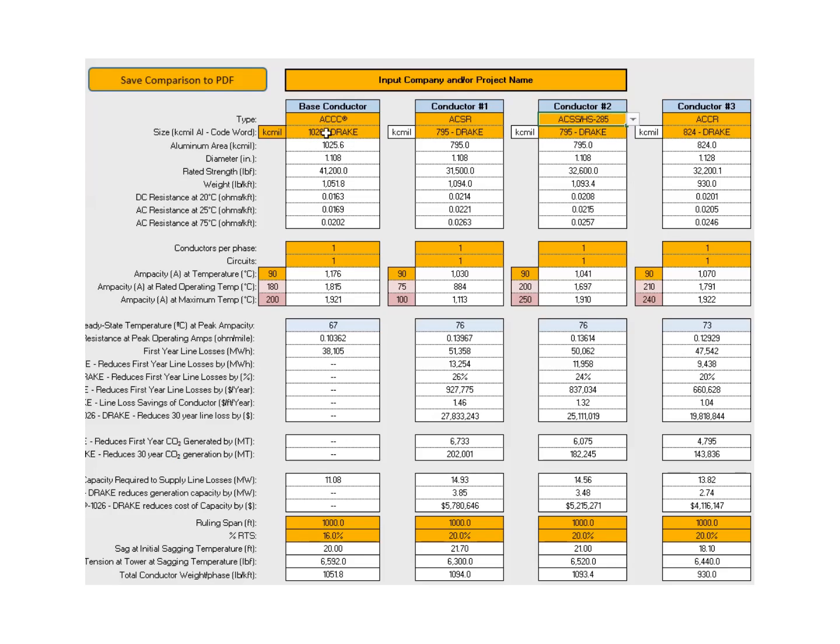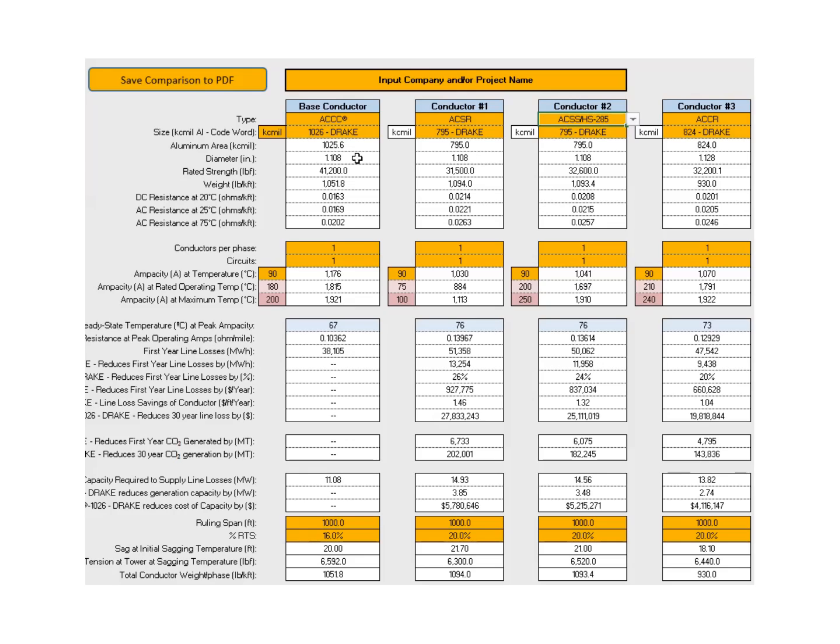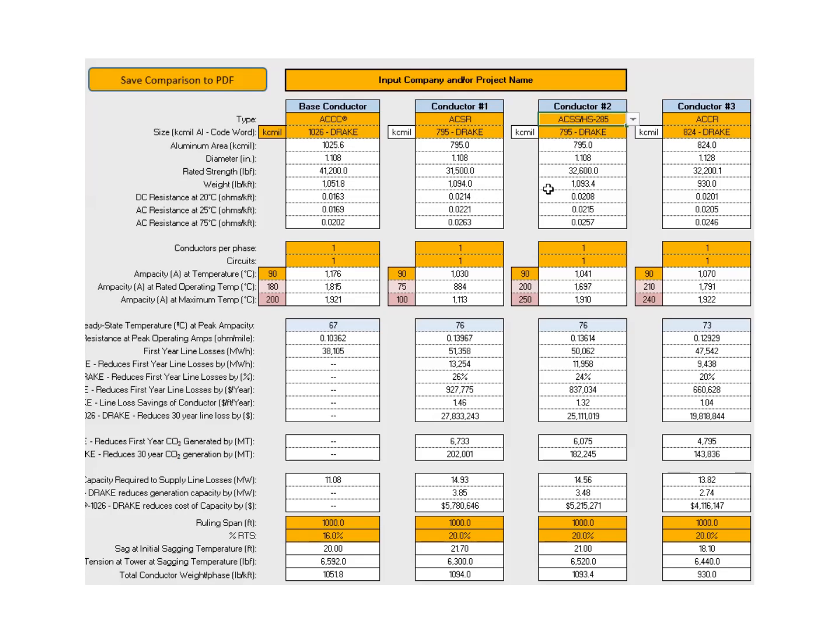You look at the upper category here, anything that's depicted in yellow or highlighted in yellow can be changed. The database is fairly substantial. It includes the cross-sectional area of the conductor, the Drake being 1025.6, ACSR 795, ACSS HS285 also 795 KC mils. The 3M product also has 824 KC mils. The diameters are depicted in the next column. 1.108 inches is a pretty standard size for a Drake conductor in terms of diameter. You can see the rated strength varies from 41,200 pounds for ACCC to 31,500 pounds for ACSR, about the same for HS285 and ACCR. It also gives us a weight per foot of 1,051 pounds per thousand for ACCC, slightly more for ACSS, similar with ACSS HS285 and 3M's product ACCR.